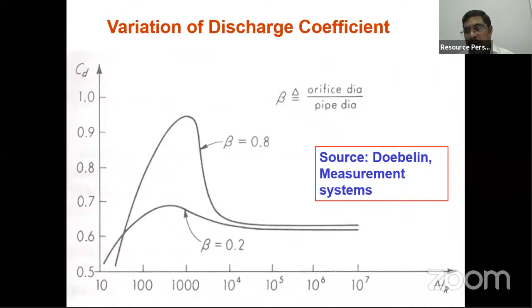That means the flow meter which is designed for one particular flow range cannot be used for another flow range. If you are using it for another flow range, you must estimate the value of the coefficient of discharge. You cannot use the same value of coefficient of discharge for a wider range. If you do, you will end up with error. So whoever is using this kind of flow meter must know how the coefficient of discharge varies with respect to velocity.